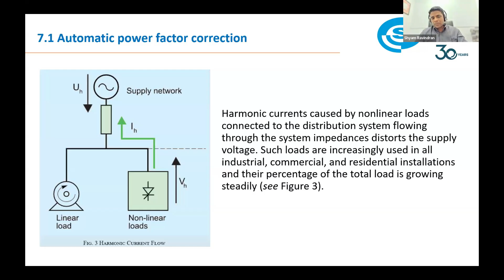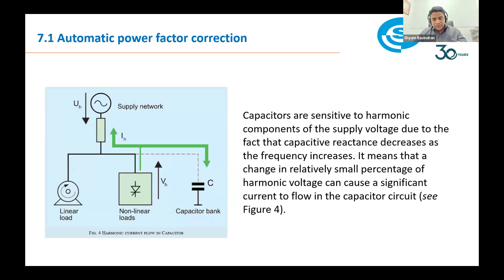Now, what is the solution? They go for automatic power factor correction, which is our APFC panels, with, let's say, three steps. We will explain it. The capacitors are sensitive to harmonic components of the supply voltage, due to the fact that capacitive reactance decreases as the frequency increases, as we know. It means that a change in a relatively small percentage of harmonic voltage can cause a significant current to flow in the capacitor circuit. So by using only a capacitor panel, we will not be able to achieve what we wanted to achieve. There is a small correction to it, which is adding a reactor to the capacitor bank.